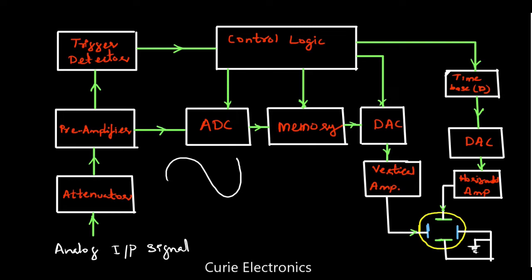From memory the data goes to a DAC. The processor, ADC, memory, and DAC are all connected to the control logic — a microprocessor or FPGA — which coordinates all these operations. From memory, the digitized data goes to a digital-to-analog converter, which reproduces and outputs an analog waveform. That analog waveform goes to a vertical amplifier. From the vertical amplifier — whether it is a CRT or TFT display — the signal drives the vertical plate. Modern oscilloscopes come with a TFT display, but here we show a CRT display.